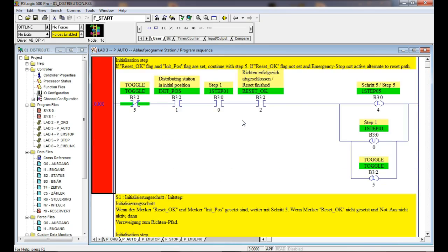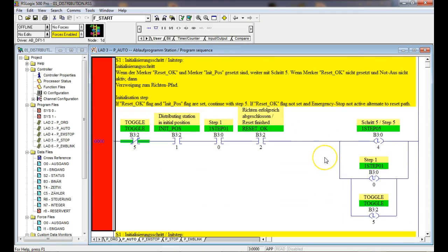And this is where you understand these internal relays, these internal coils, we call them. Because when you get into a complicated control system, 90% of the relays are in there for nothing but decision making. That's all they're in there for. In real life, with motor controls, all those control relays, you have to wire them up. But none of their contacts ever leave the control circuit. None of them go into the power circuit.